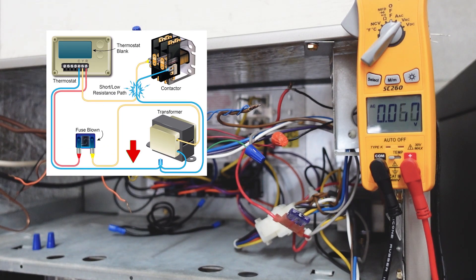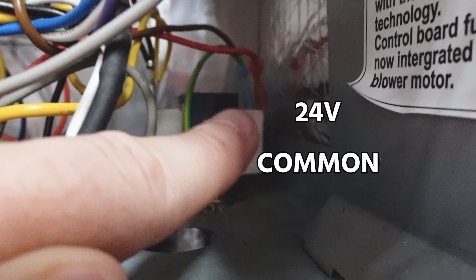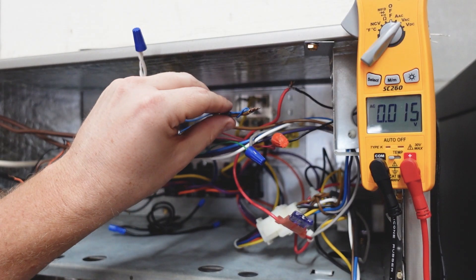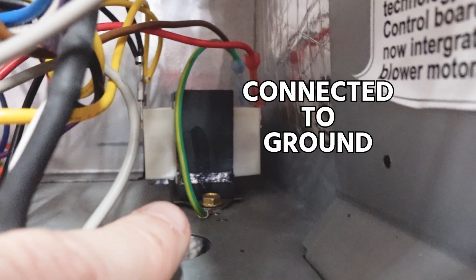And then on the other side of our transformer secondary, we have a 24 volt common, which is this brown wire here. Now this transformer has what we call a grounded secondary. So the common on the secondary is actually connected to ground via a green wire.